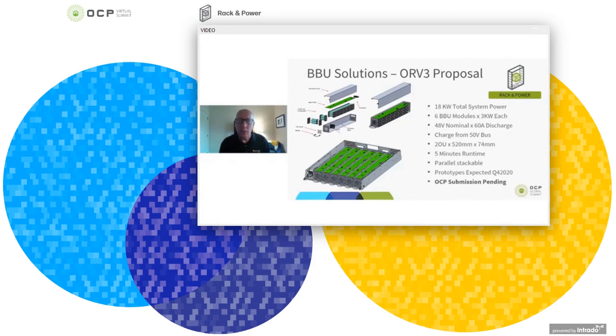Each one of these modules is 48 volt and will support a 60 amp discharge. The actual regulation is on a different module that the battery backup unit plugs into, which supports charging and discharging at that 48 volt plus or minus 1% output.